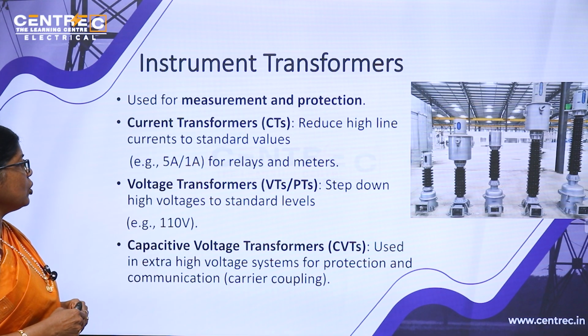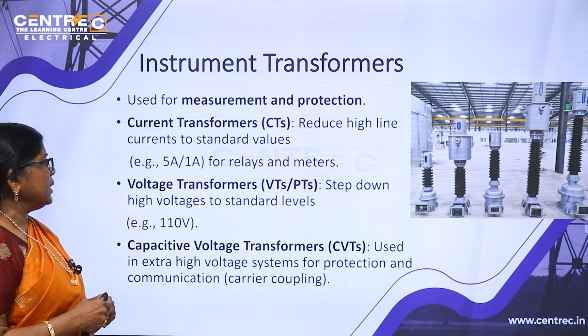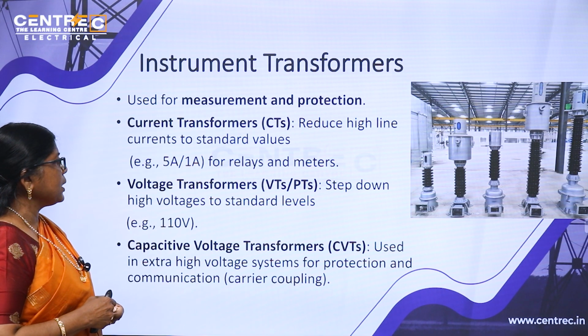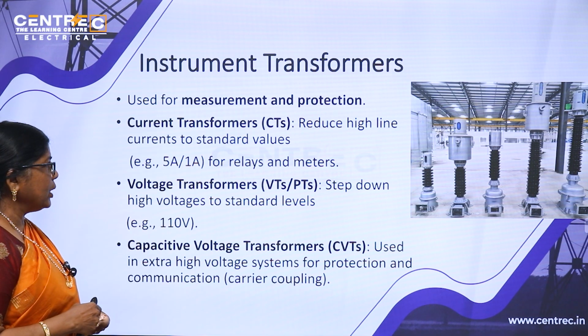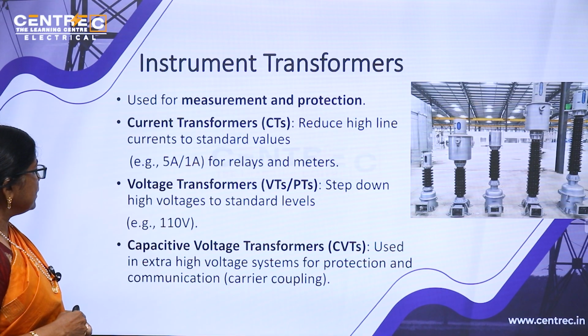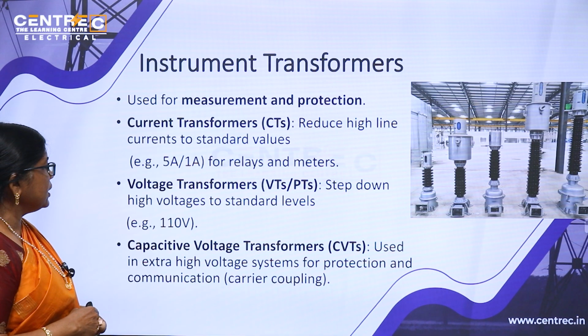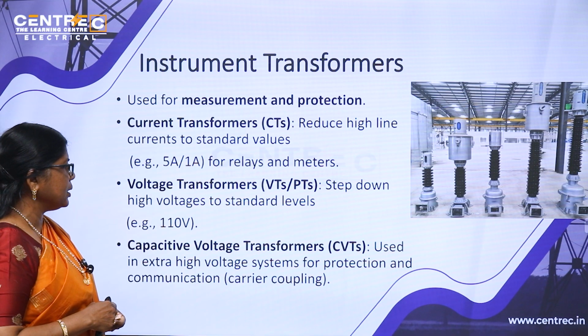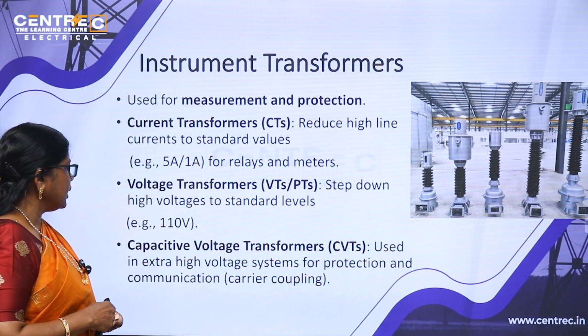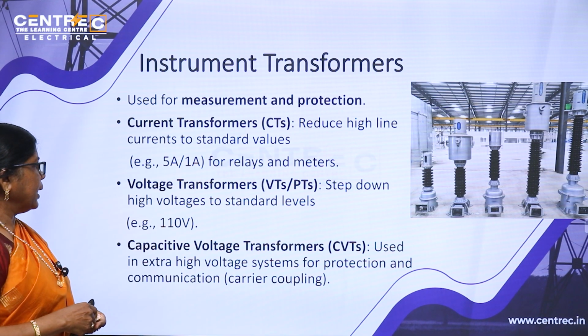Then voltage transformers, VTs and PTs, step down high voltage to standard levels, for example 110 volts. Capacitive voltage transformers, CVTs, are used in extra high voltage systems for protection and communication, that is carrier coupling.